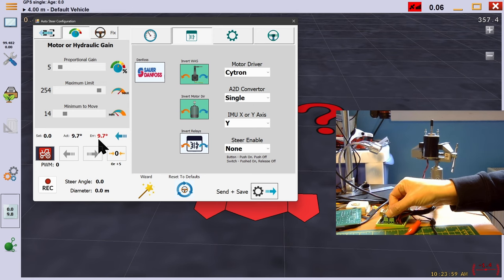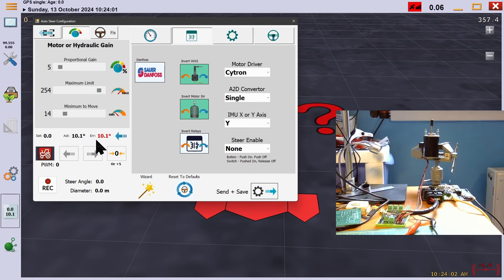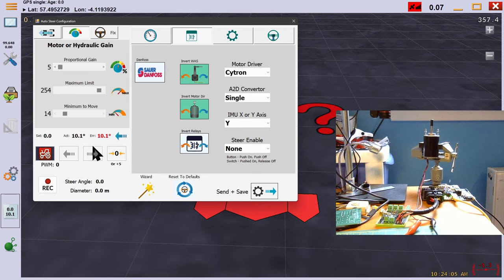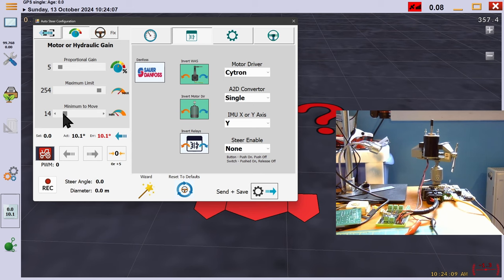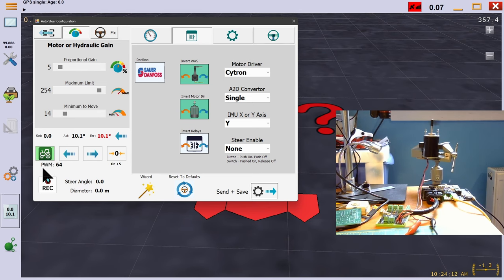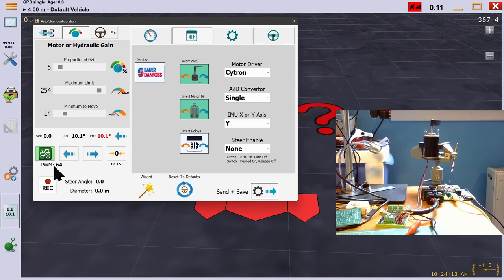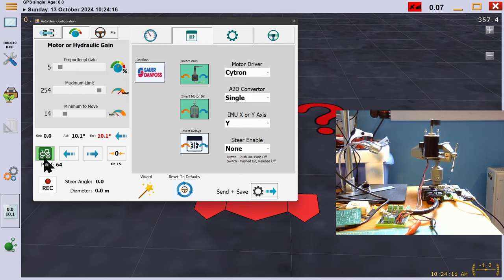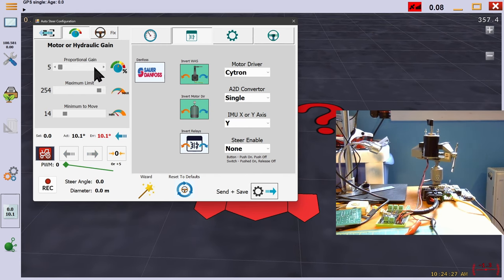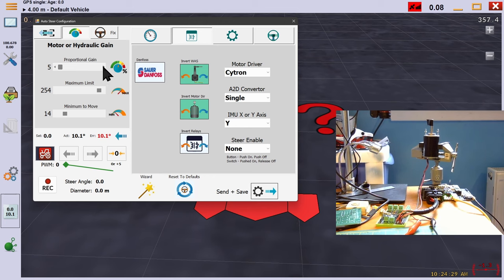Let's set our actual wheel angle to around 10 degrees. With a proportional gain of 5, we multiply by the error and get 50. We add the minimum at 14, and our output is of course 64. A good starting figure for proportional gain for a real machine would be around 20.